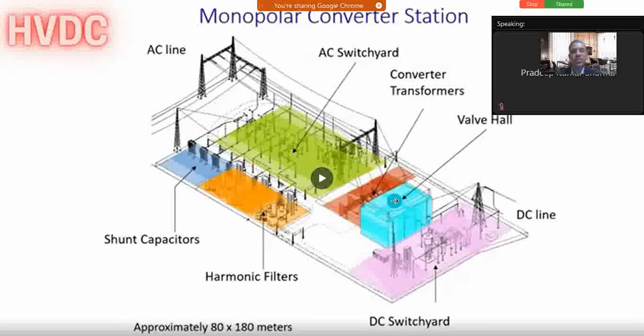Because conventional HVDC, thyristor based HVDC, needed 50 to 60% reactive power at the terminal station itself, that conversion is possible after applying that much reactive power. So this is a conventional technology. These are the thyristor valves, and generally suspended structures are used, but now there is a development where mounted structure valves are also coming. So there is much more evolution.